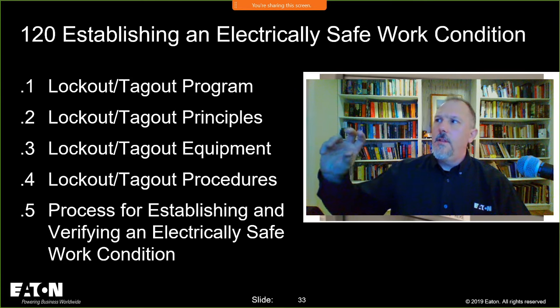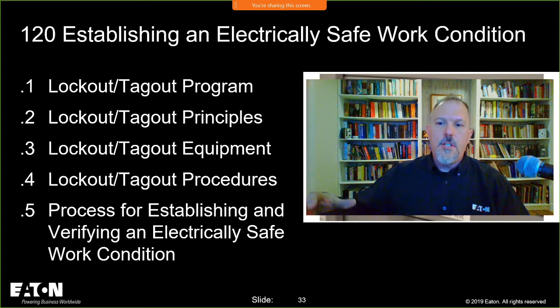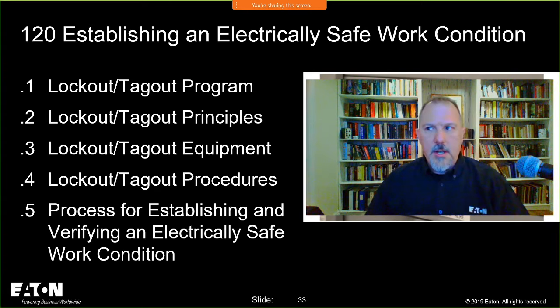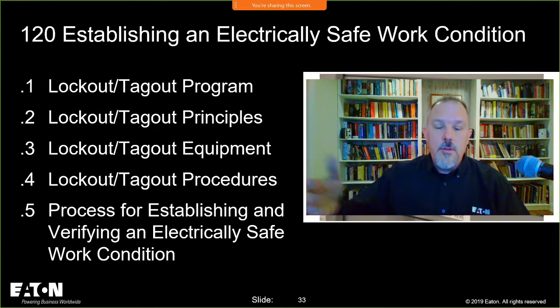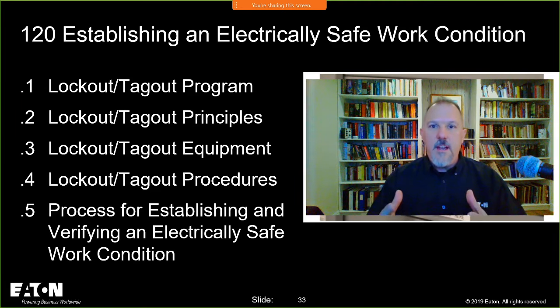If you look at how it's laid out, dot one is lockout tagout. You have the general overview of lockout tagout, the principles behind it, and the equipment that you're supposed to use. You have the procedures, so you have simple procedures, or you have complex. You may have in your power distribution system one overcurrent device or one switch that is supplying the equipment that you're working on. When you turn it off, you're going to put your lock and tag out on that one switch.